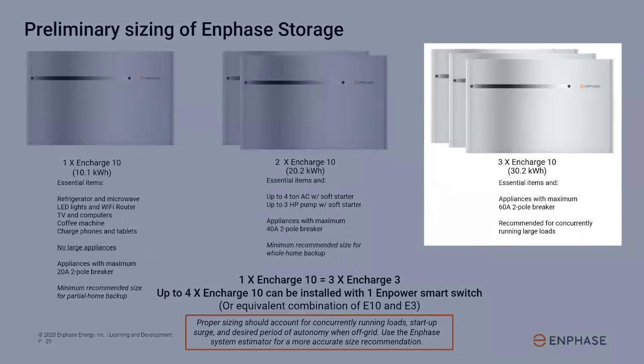And then lastly, if you have a large home that has multiple large loads that must run continuously and simultaneously, that's when you are getting into a larger system size like 3 or 4 of the Encharge 10s. Proper system sizing needs to account for concurrently running loads, startup surge, which we'll cover in more detail in the next few slides, as well as the desired period of autonomy, or the number of hours that the system needs to support the home when disconnected from the grid.